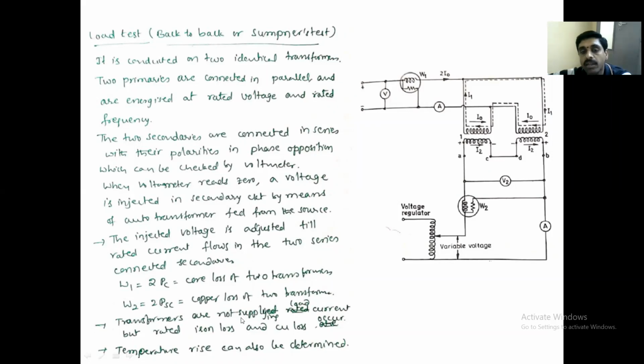So the transformers are not supplying the load current, but rated iron losses and copper loss are there. Here we are not loading the transformers, full load you are not applying. So simply it is an indirect test. You are applying the rated current and the rated voltage to identical transformers. At the same time, they are not actually loaded. So we are finding copper loss and iron loss.